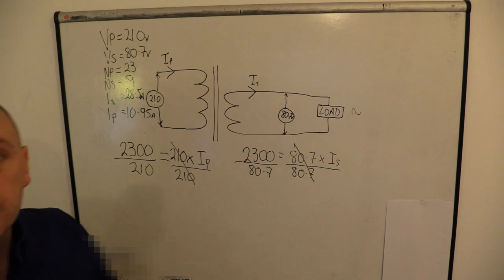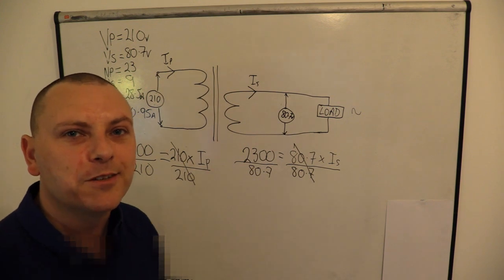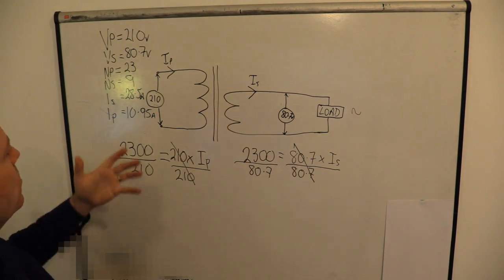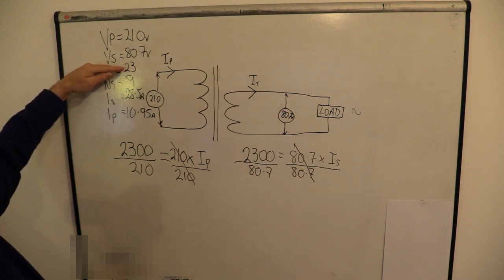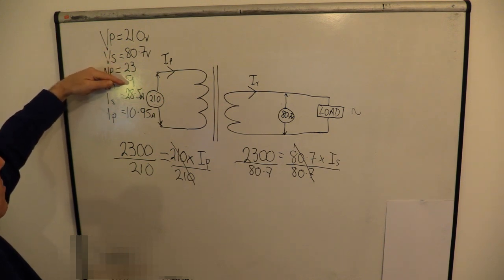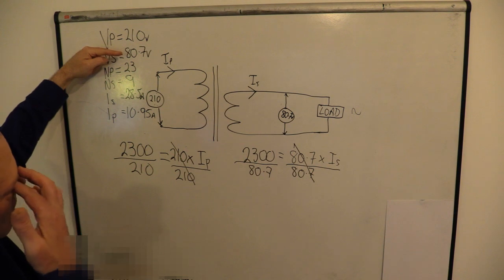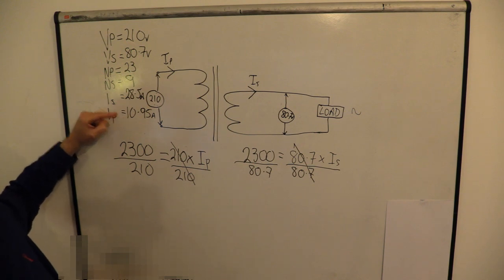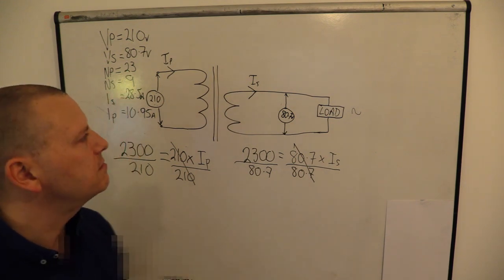Let's have a look at this and see if it makes sense, because it's really important to go back over your numbers and check. We know that if the voltage comes down, the current is going to go up. The primary turns were 23 and secondary were 9 - so it's a step-down transformer and the voltages are stepping down. That would mean the current would have to come up. Primary current was 10.95 amps and secondary has gone up to 28.5 amps. So all of those check out - they all work.